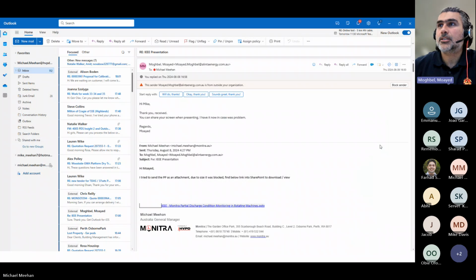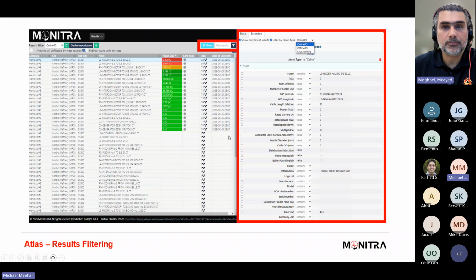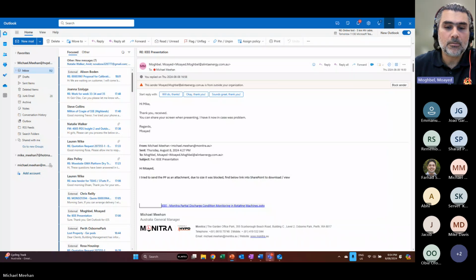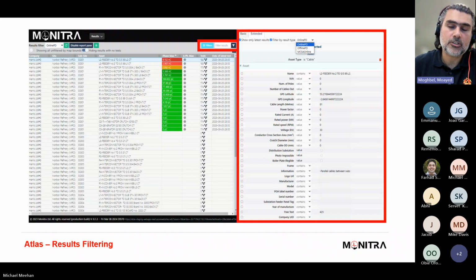Mike thanks you for the presentation. A quick question: you mentioned that the majority of the faults in the generator are related to stator faults. Yes, we had some bearing related faults as well, and partial discharge. Can you give more detail on what could be bearing related, and also the rotor related partial discharge? They were, if I remember, only 10%, much less than the stator.